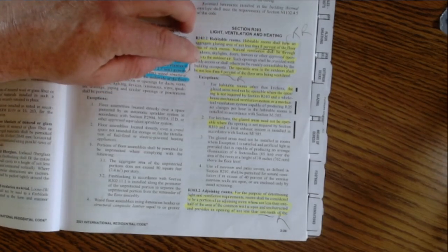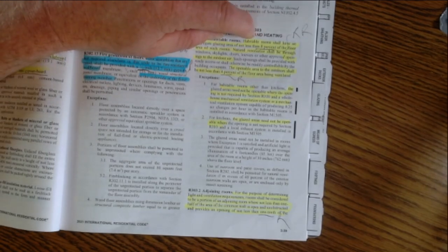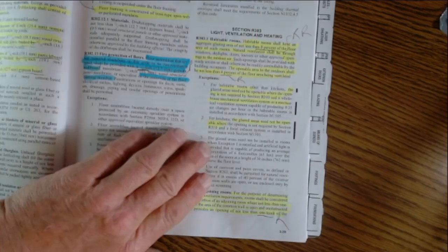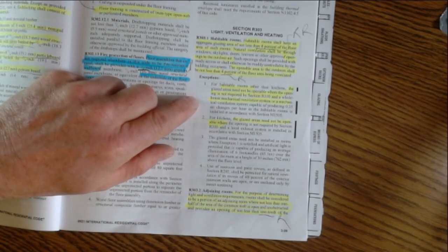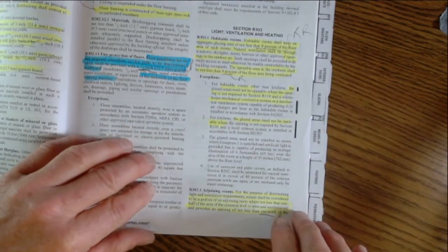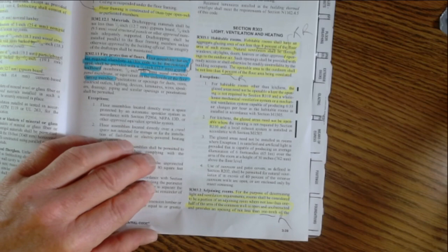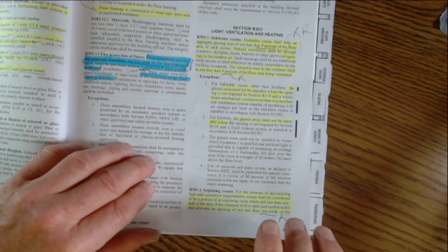You can have like 20 CFM continuous for your vent, or 50 CFM intermittent with the switch. You could also have a window that's openable, and I think you have to have at least 3 square feet on that, so you don't have to have the mechanical vent. Know this section. It'll catch you if you don't know it. Just know some of those details. But the point is, you don't need an openable window or a window period in a bathroom.